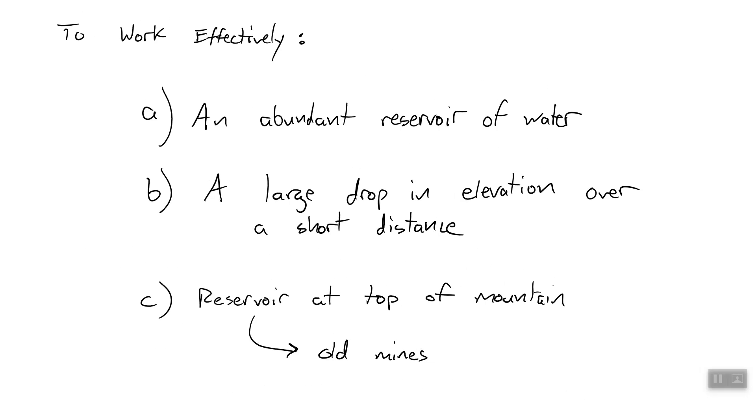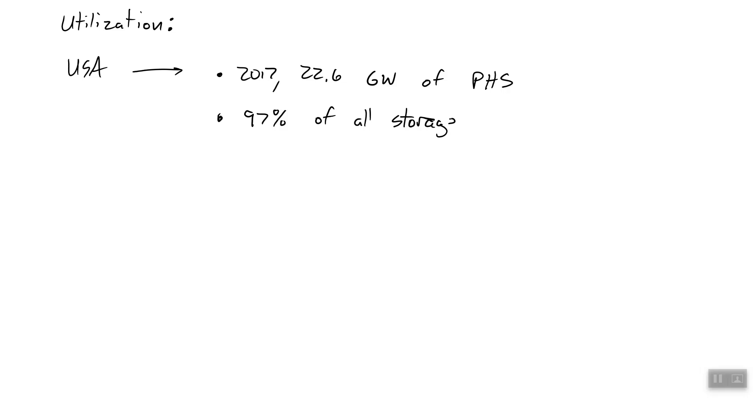Okay, finally, let's talk about actual utilization. Honestly, this is a great idea. It's a little hard because we can only develop so much of it, right? There's only so many places where you have an abundant reservoir of water, a large drop in elevation, and some convenient way already established to store the water at the top. So in the United States of America, in 2017, we had 22.6 gigawatts of pumped hydro storage installed, which represented 97% of all storage capability, all grid storage capability. So I mean it is, as we saw initially, the best way to store energy and extract that energy. And so it is what we use almost exclusively.